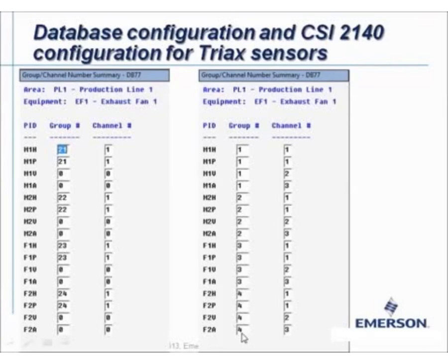If there are more than 4 bearing locations in your machine, for every bearing location you simply continue with the next available number. When you start again in the next machine, you can restart with group number 1. And inside every group, horizontal and peak view horizontal is 1, vertical is 2, and axial is 3.